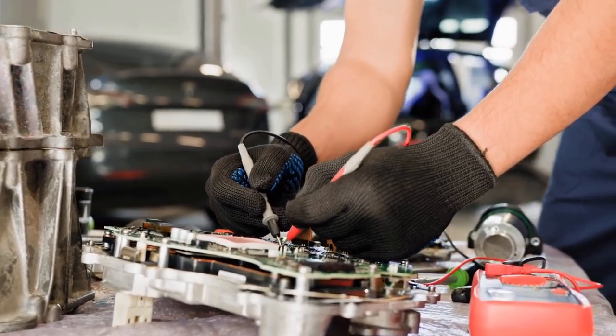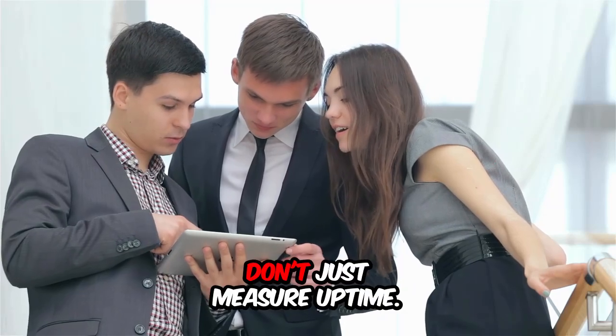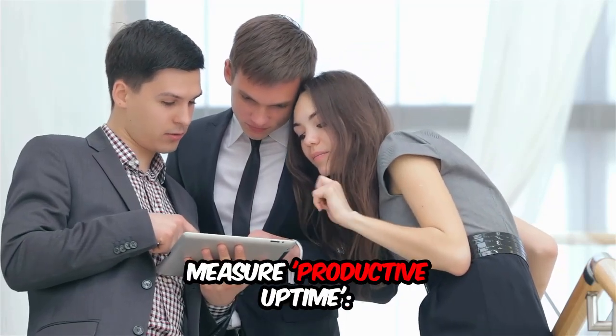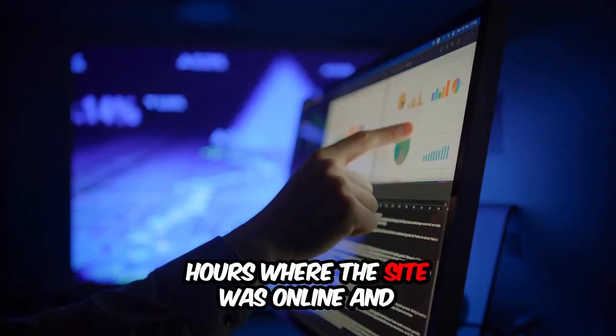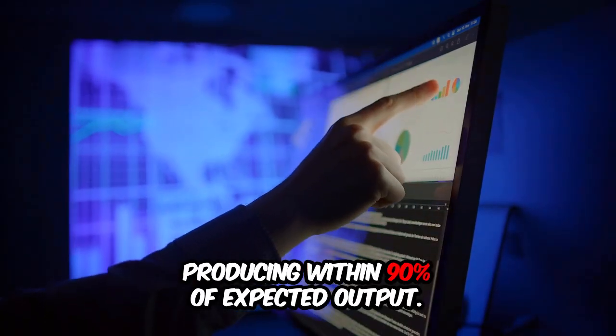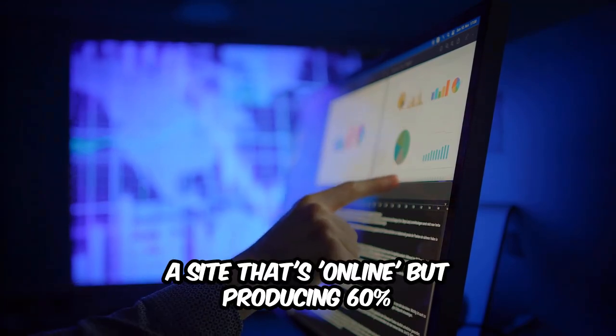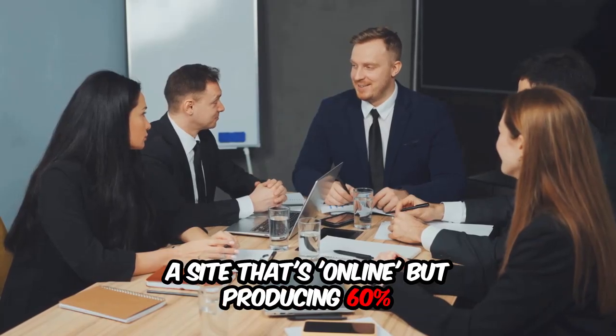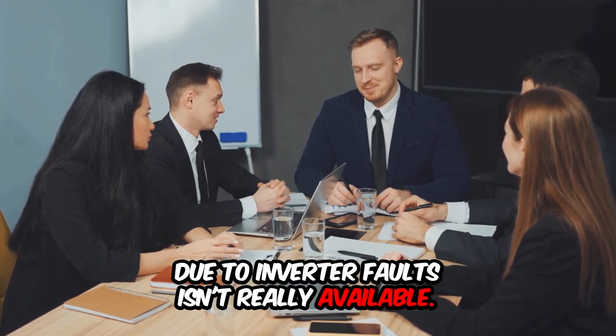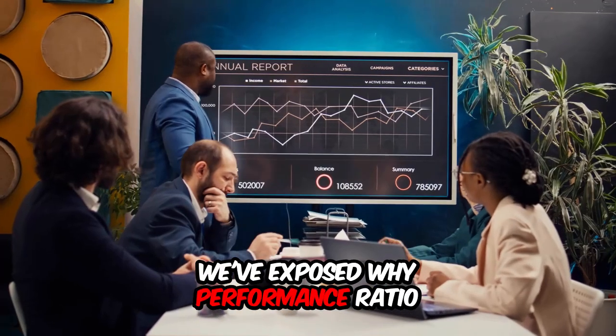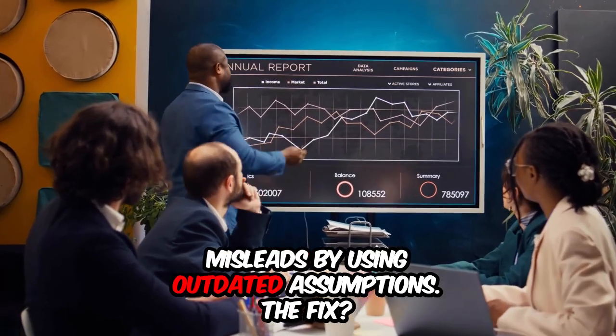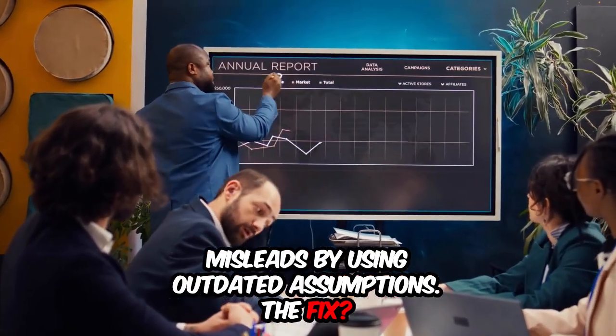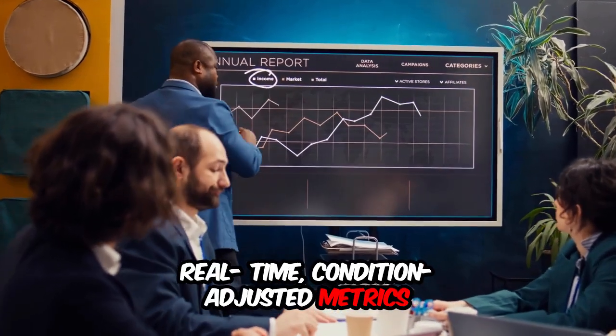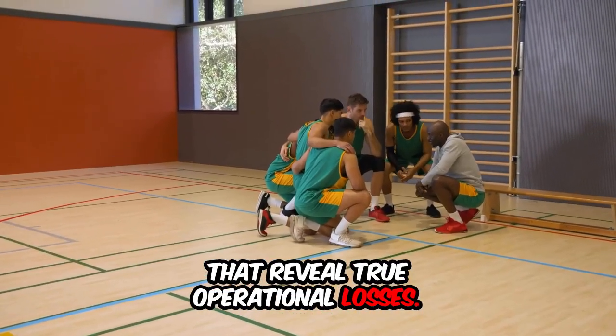Metric number 4, availability-weighted performance. Don't just measure uptime, measure productive uptime, hours where the site was online and producing within 90% of expected output. A site that's online but producing 60% due to inverter faults isn't really available. We've exposed why performance ratio misleads by using outdated assumptions. The fix? Real-time, condition-adjusted metrics that reveal true operational losses.